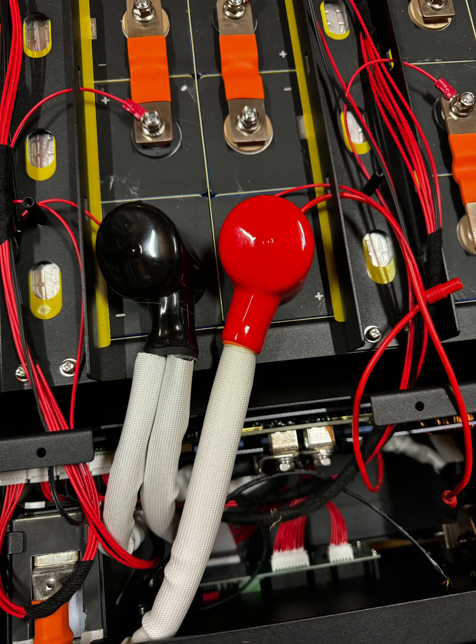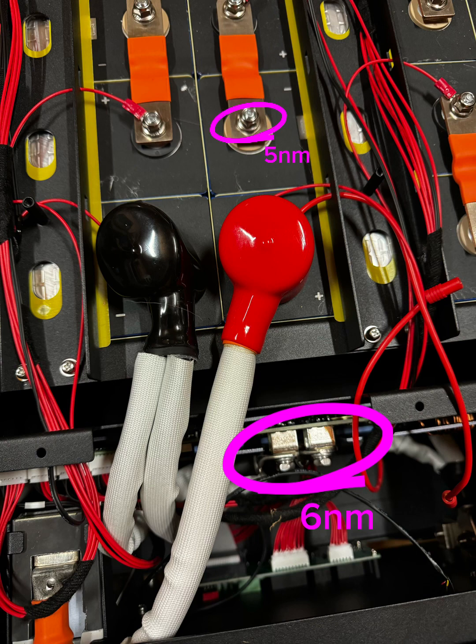It's now time to check the connections on the front plate of the BMS to 6 Newton meters, top and bottom, and the bus bars each to 5 Newton meters.